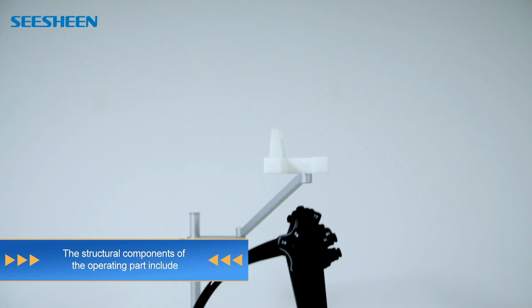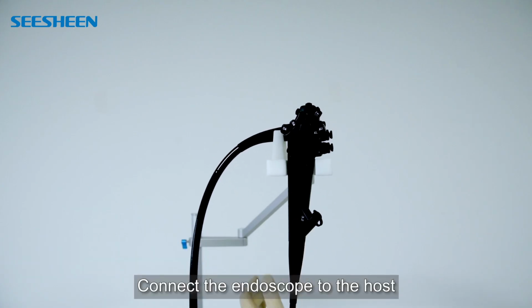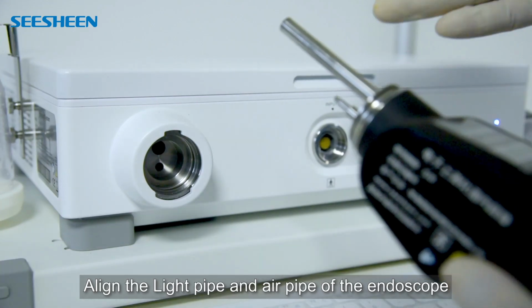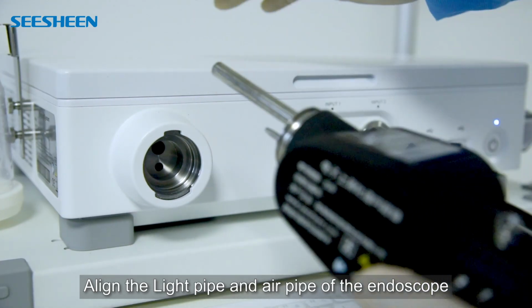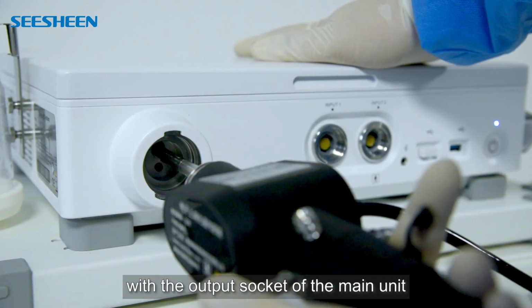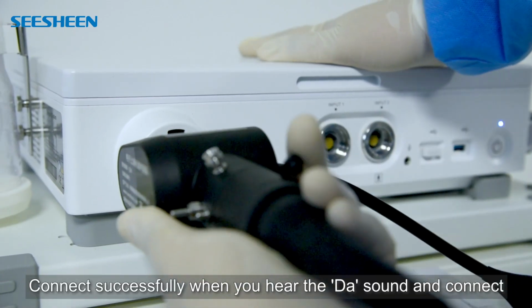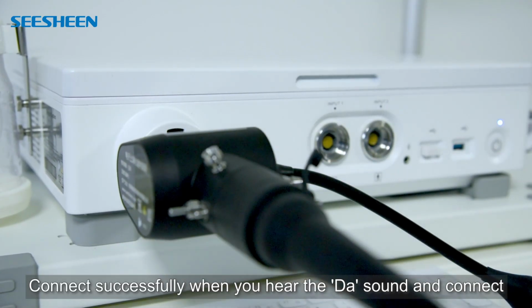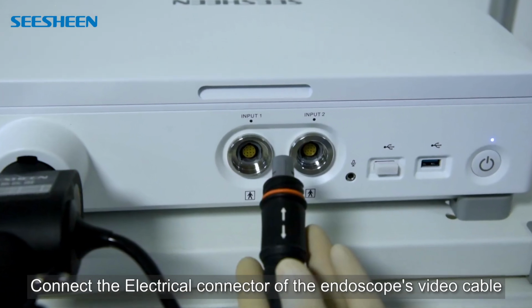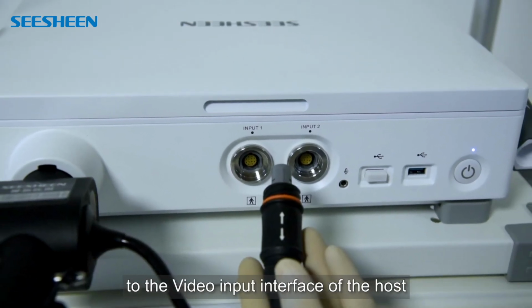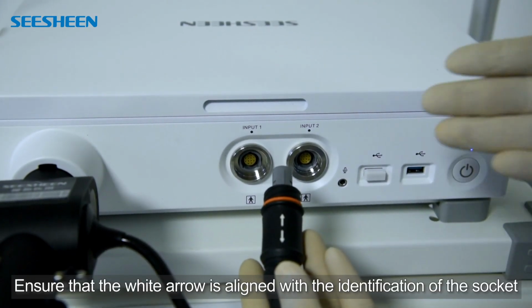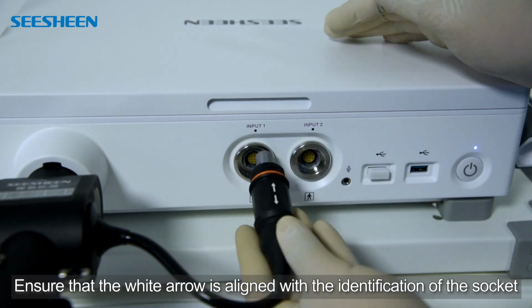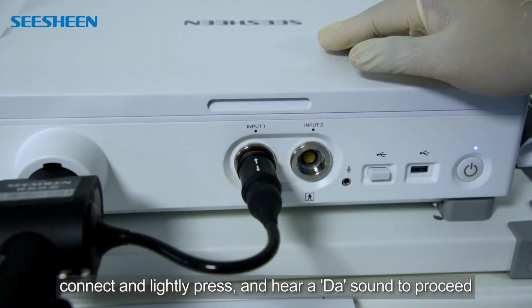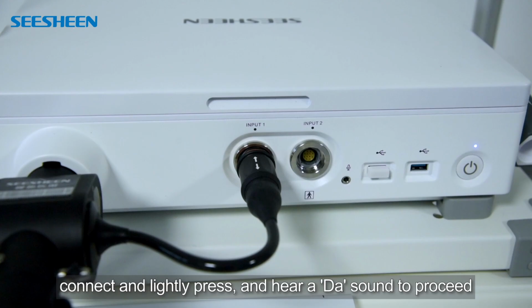Equipment connection and operation function demonstration. Connect the endoscope to the host. Align the light pipe and air pipe of the endoscope with the output socket of the main unit. The connection is successful when you hear a "da" sound. Connect the electrical connector of the endoscope's video cable to the video input interface of the host. Ensure that the white arrow is aligned with the identification of the socket. Connect and lightly press, and proceed when you hear a "da" sound.